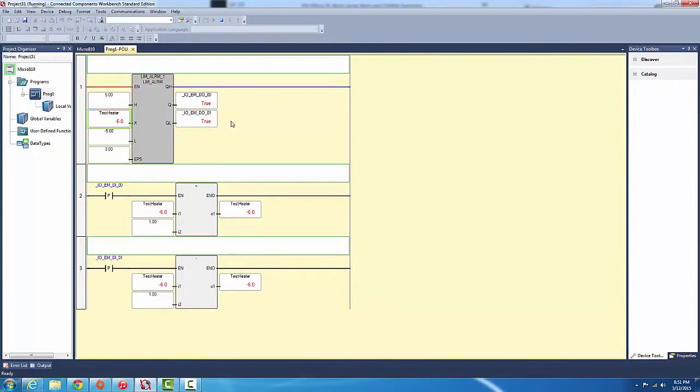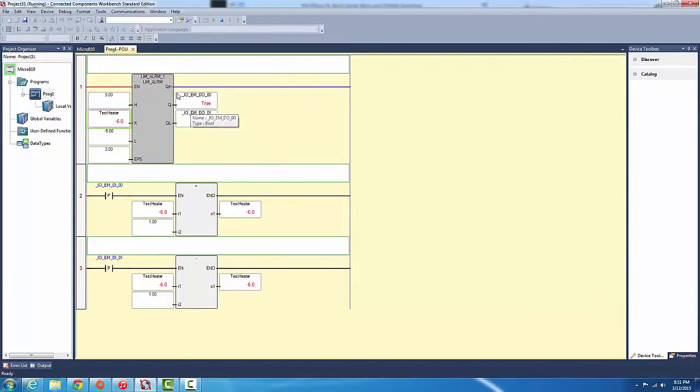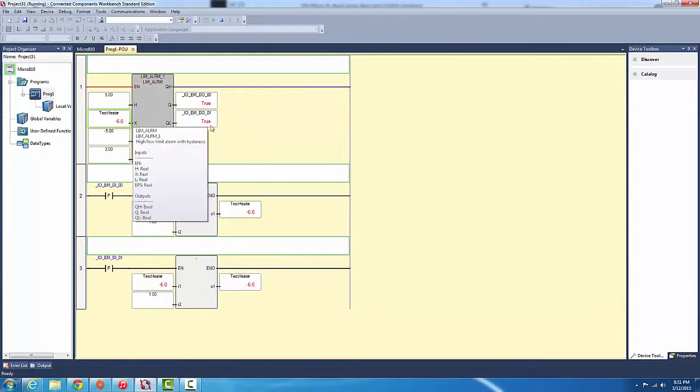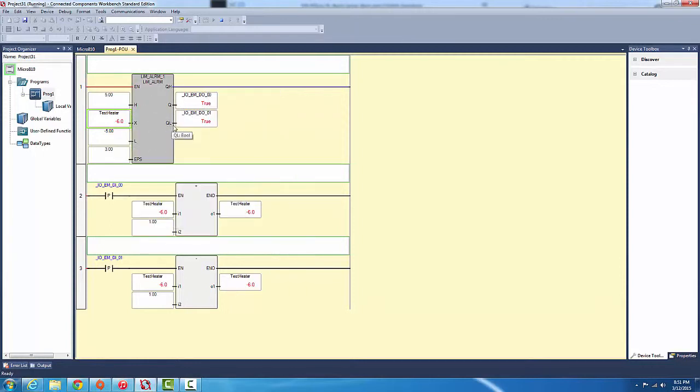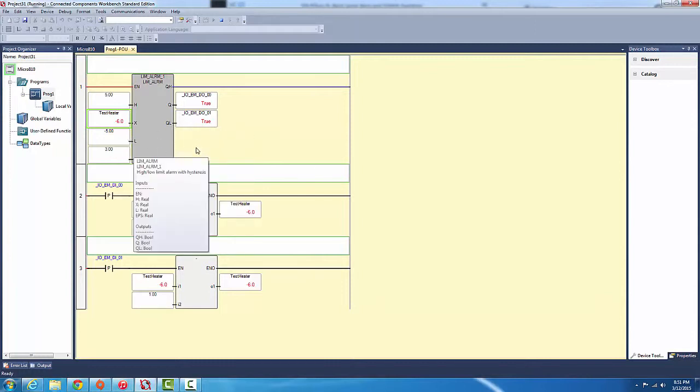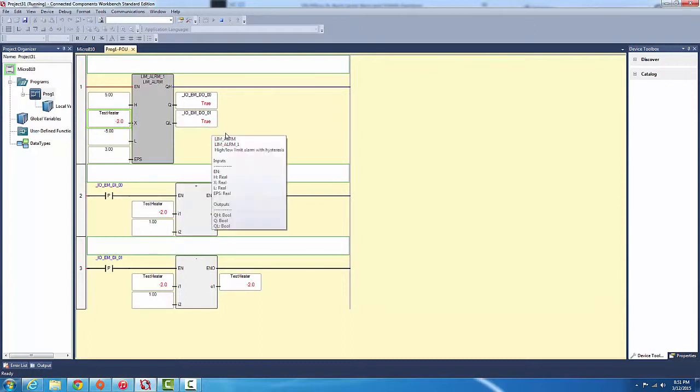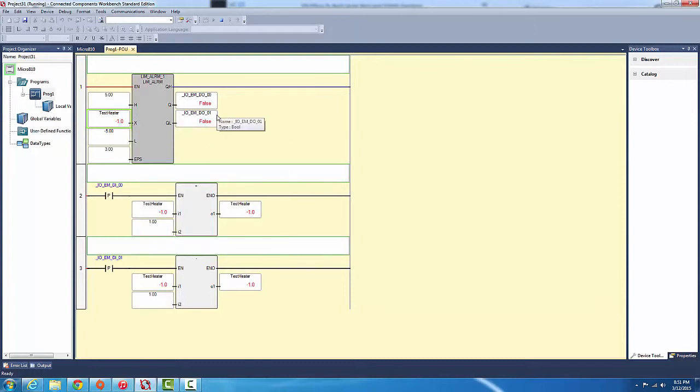Now we want to see if the low limit works. This should turn on. See, both of them go true, but this doesn't close. So QH equals Q, so high means this closes, and Q means it's out of limit. And QL means it's low. When we go back to negative one, it should go false again, which is correct. And that's basically how the limit alarm instruction block works.